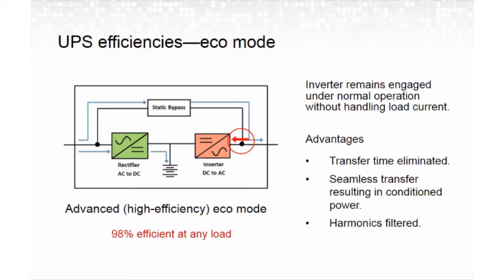And that also helps with conditioning the power. Because it's a seamless transfer, if there's any fluctuation in power, that load can be automatically transferred through the double conversion and then reconditioning the power. So you won't have that unconditioned power going to the source. And also it helps with harmonics. Because the inverter is engaged, it can absorb and filter out some of the harmonics, even though the load is not being carried through the inverter.